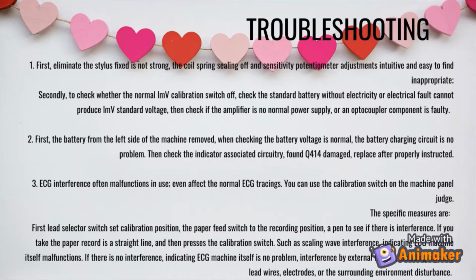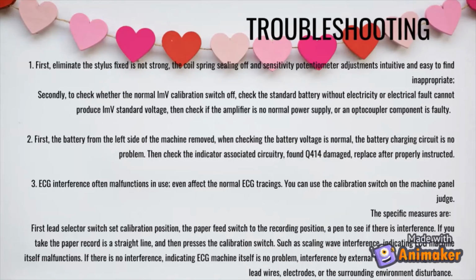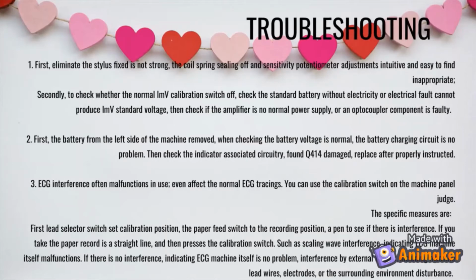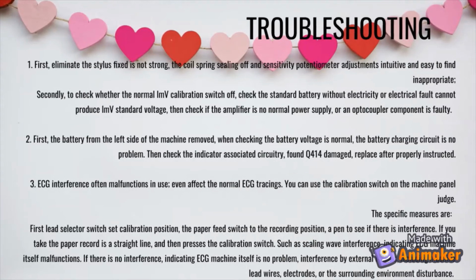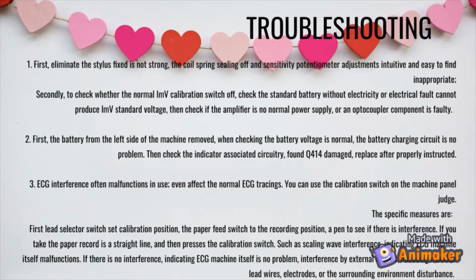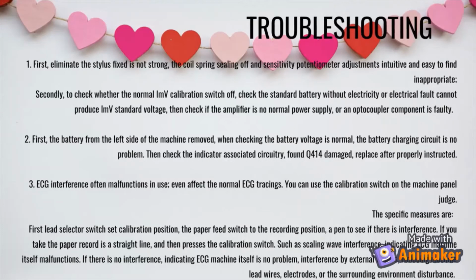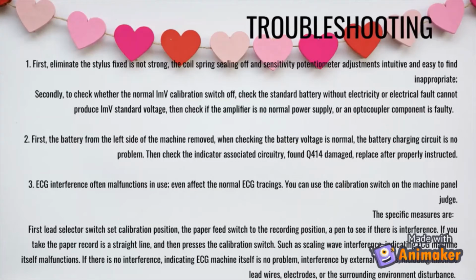First, remove the battery from the left side of the machine. When checking, if the battery voltage is normal, the battery charging circuit has no problem. ECG interference often malfunctions in use, even affecting the normal ECG tracing. You can use the calibration switch on the machine panel to judge. The specific measures are: first, set the lead selector switch to the calibration position. Set the paper feed switch to the recording position.